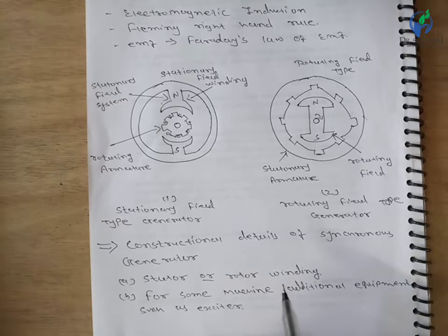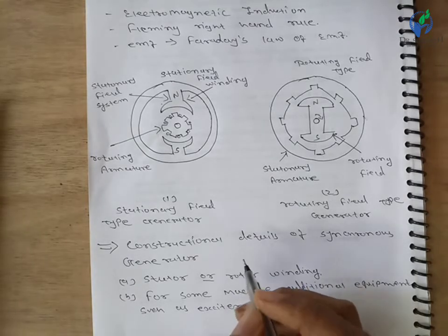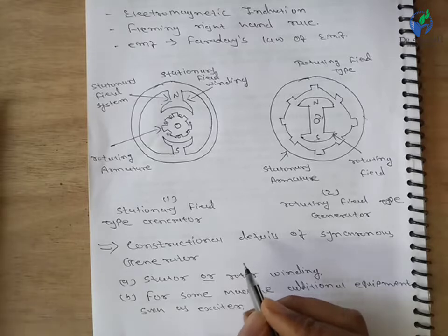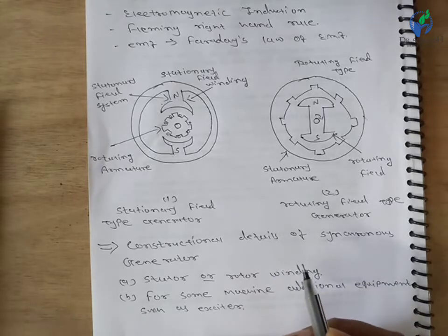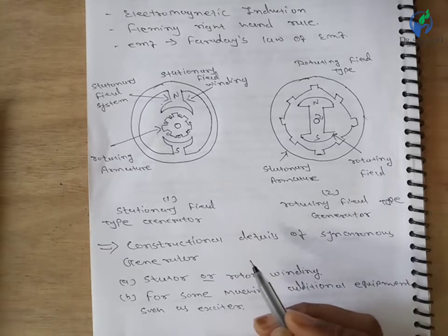The rotating field system is almost universal, especially for large capacity alternators. This helps to have a winding installed for high voltage on the stationary armature. The field system has a low voltage and low power winding which can be easily insulated and supplied by two slip rings. This also helps to limit the size of the machine.